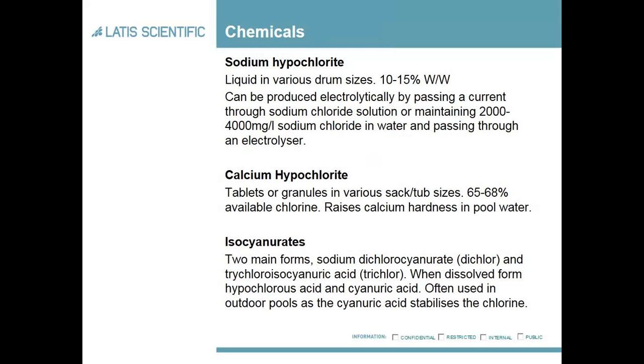So what do we use as our chlorine donors to disinfect the pool? One of the main products is sodium hypochlorite, particularly in areas where you have a higher hardness of water. It usually comes in liquid form at around 15% weight-to-weight. You can also generate chlorine electrolytically by passing a current through a sodium chloride solution, maintaining a level of 2,000 to 4,000 milligrams of sodium chloride.